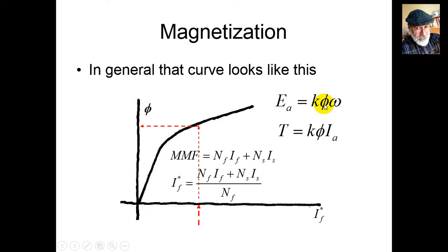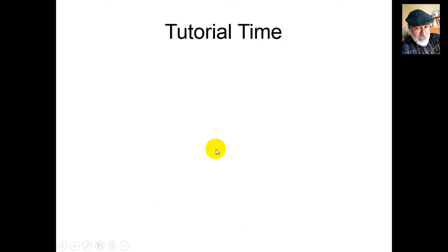In both formulas, you see Kφ times omega, and Kφ times armature current. The manufacturer decided to multiply the vertical axis by K, but also by omega - specifically, omega test, the test velocity used to measure the machine. So the curve reports the voltage induced in the armature for a given IF* if the machine had been rotating at omega test, given as RPM.